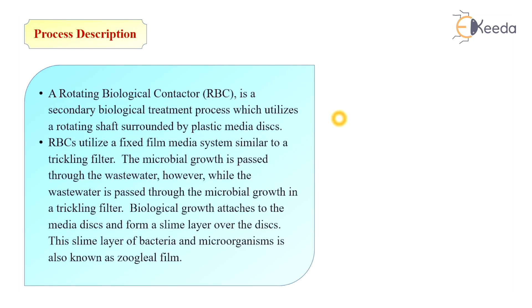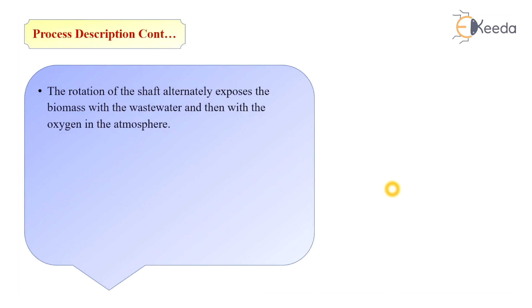In the trickling filter, the wastewater is passed through the microbial growth — that is the key difference between the two. In RBCs, the media or disc is rotating and immersed in the wastewater, so the microbial growth passes through the wastewater. It is important to understand this difference between the two units.